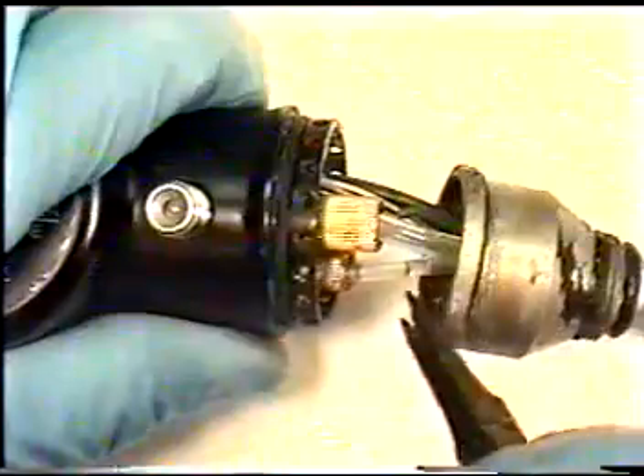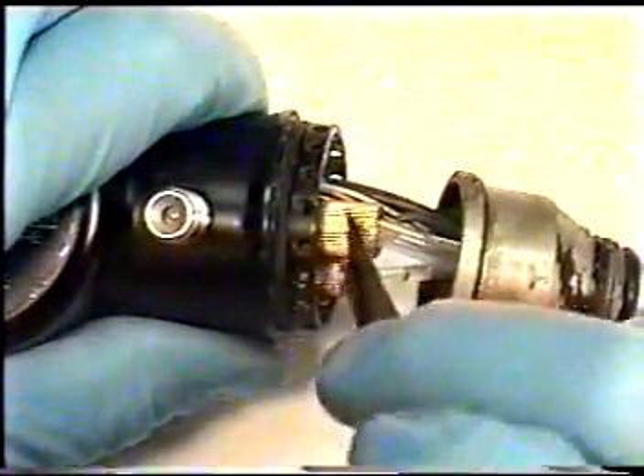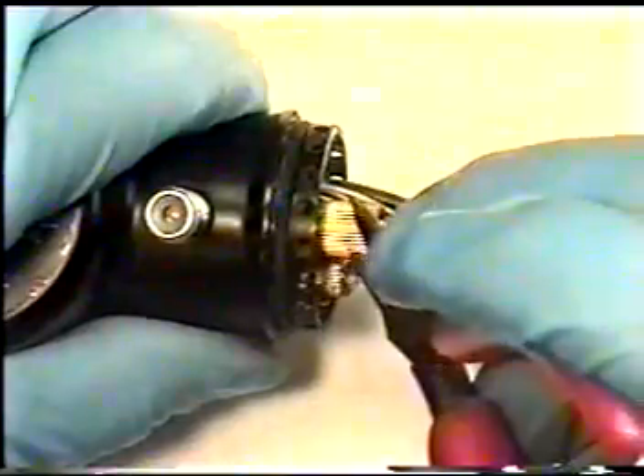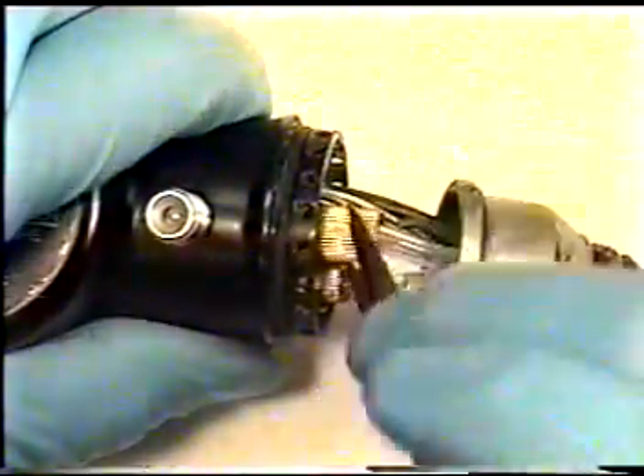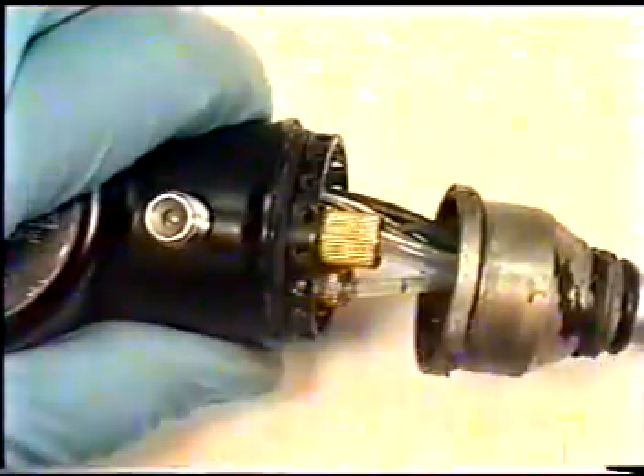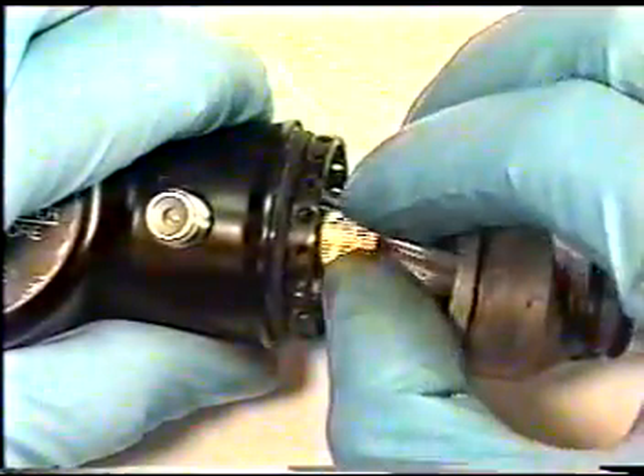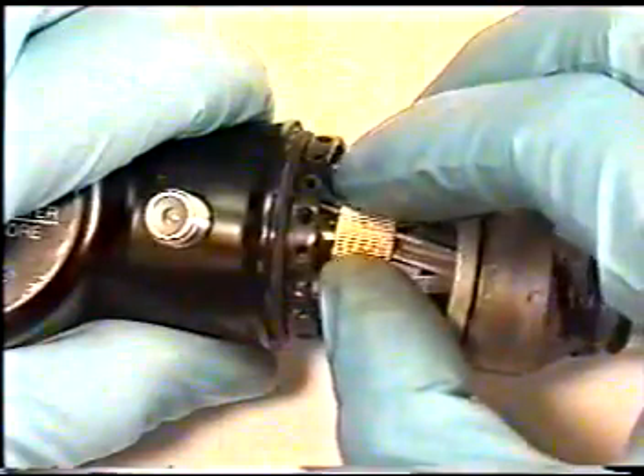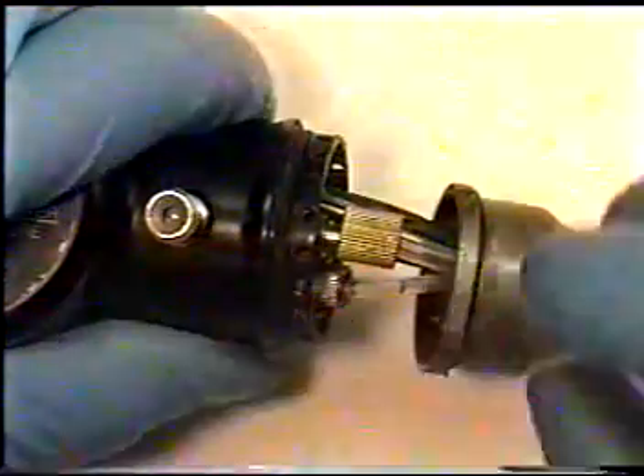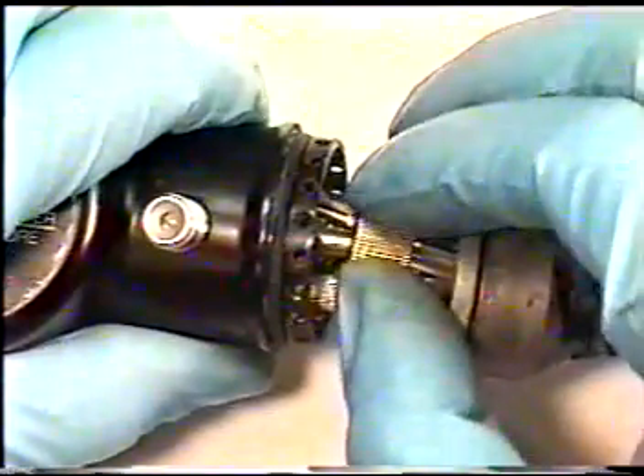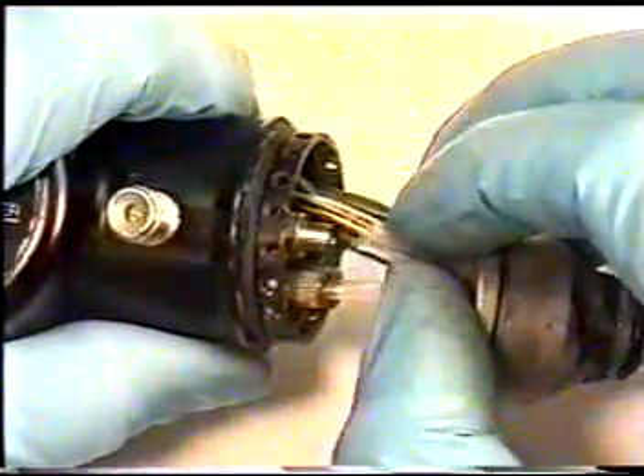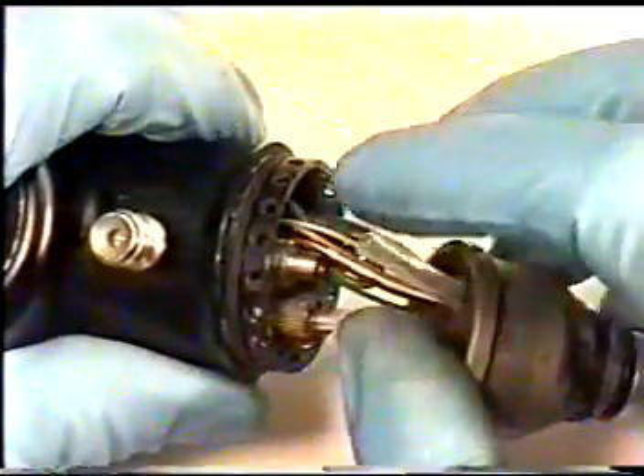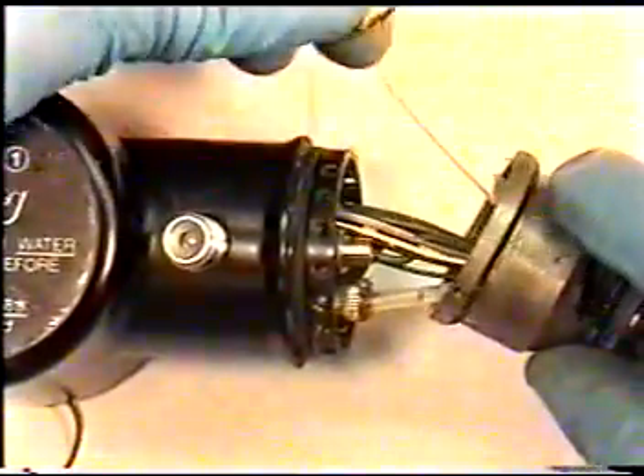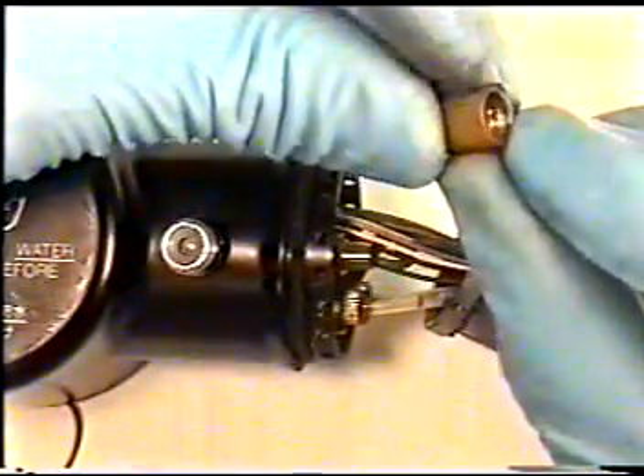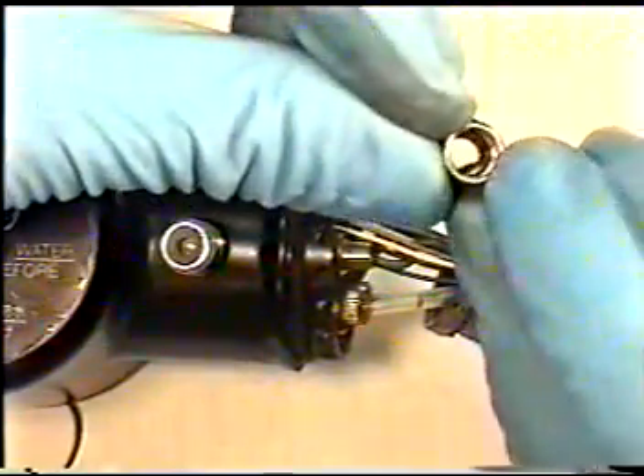Utilizing a pair of needle nose pliers, carefully unscrew counterclockwise the suction channel retaining ferrules. Once they are loosened, you can remove with your fingers. Also pull off your suction channel from your suction channel fitting. Retain the ferrules for reassembly. There are two pieces, an external piece and your internal ferrule.